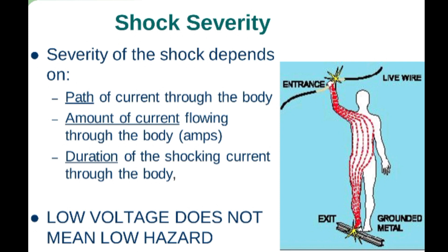Dangers of electrical shock. Current above 10 mA can paralyze or freeze muscles. Current more than 75 mA can cause a rapid, ineffective heartbeat. Death will occur in a few minutes unless a defibrillator is used. 75 mA is not much current. A small power drill uses 30 times as much.